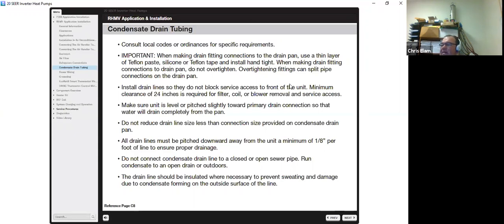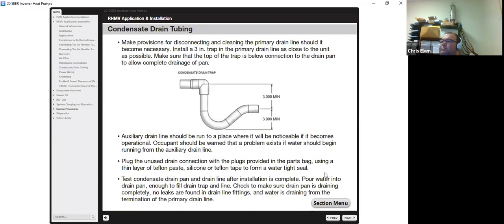The drain line should be insulated where necessary to prevent sweating and damage due to condensate forming on the outside of the surface line. A big one: the condensate trap has to be installed. If not, the bulk of your water will just flow over your drain pan and will not drain. So make provisions for disconnecting and clearing the primary drain line should it become necessary. Install a 3-inch trap in the primary drain line as close to the unit as possible. Make sure the top of the trap is below the connection to the drain pan to allow complete drain of the pan.